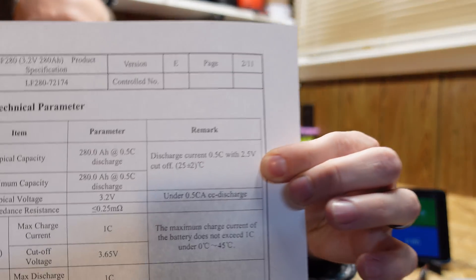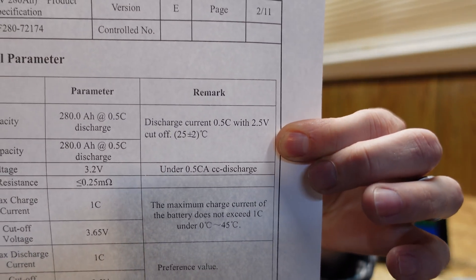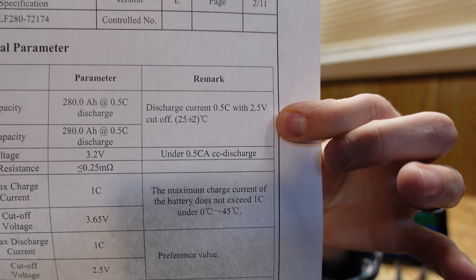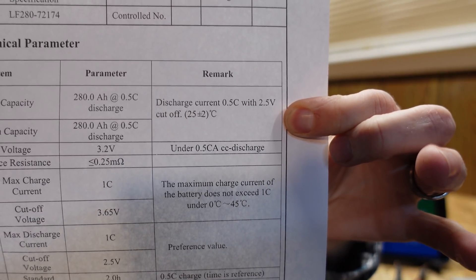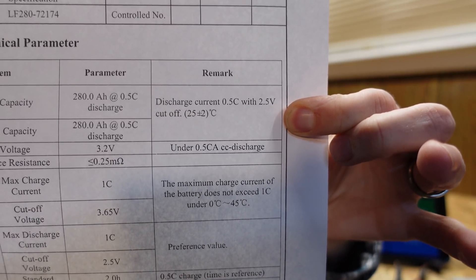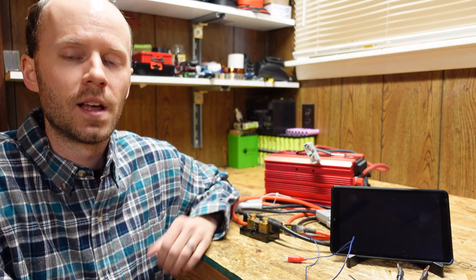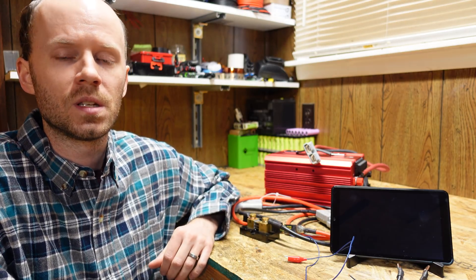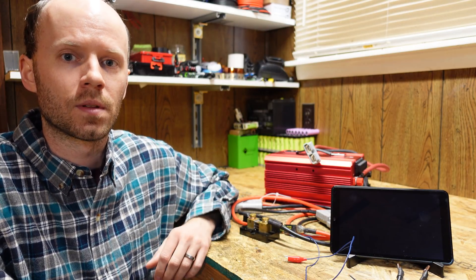If we take a look at the data sheet for the EVE 280 amp hour batteries, we can see the standard test is a 0.5 C rate down to 2.5 volts per cell. I am seeing the 0.5 C discharge rate more and more frequently now, specifically in the aluminum case prismatic larger capacity cells. However, I still use 0.2 C rate in my tests because it covers a broader area of form factors and chemistries and so forth.